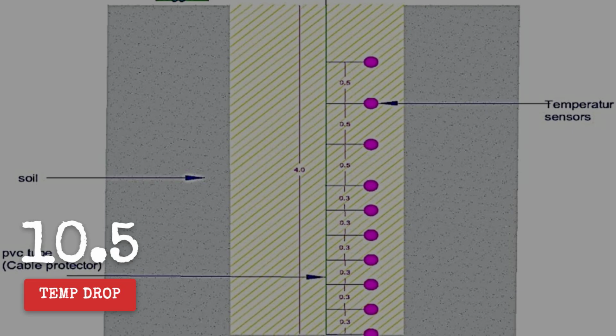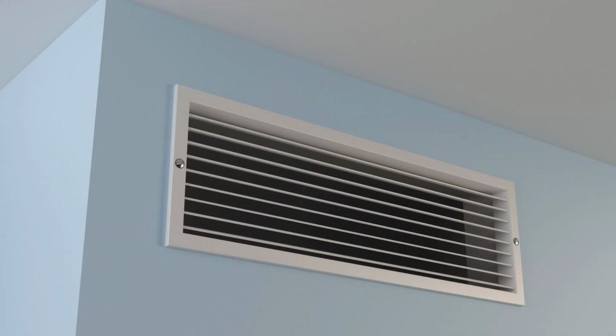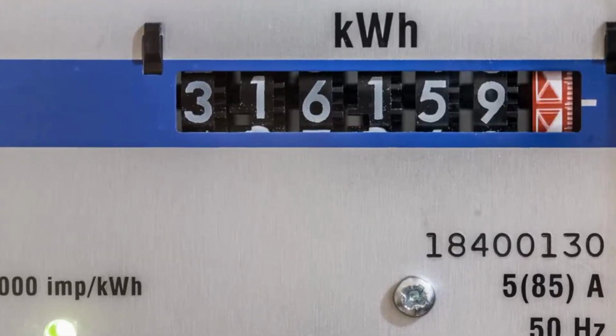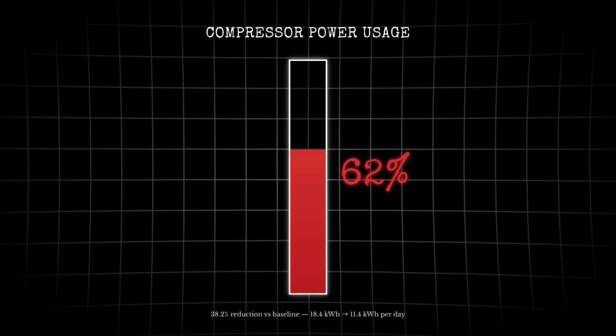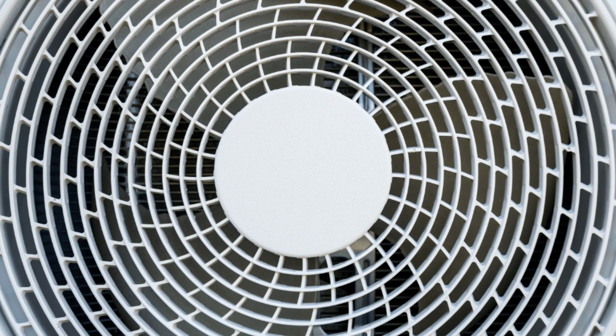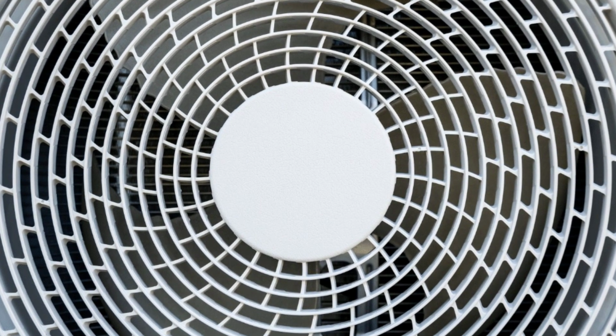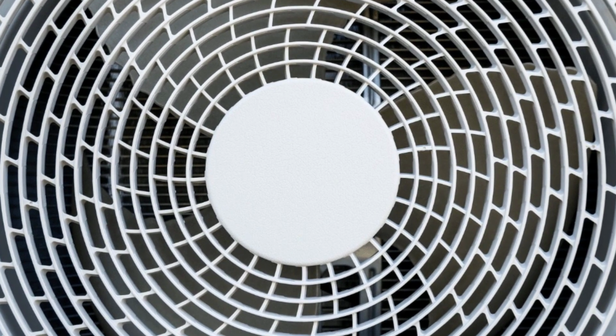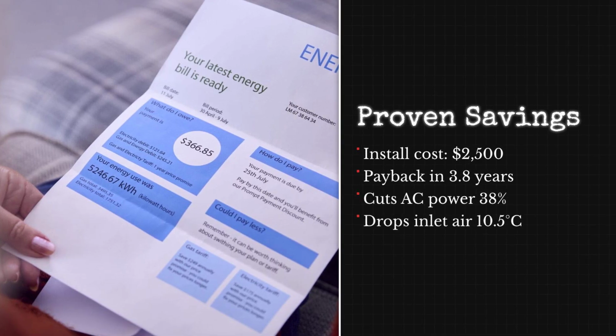Sensors at the inlet and outlet showed a temperature drop of 10.5 degrees Celsius, and air entered the home noticeably cooler than the ambient environment. The impact on energy use was just as clear. Electrical monitoring revealed a 38.2% reduction in compressor power for the home's standard HVAC unit. With a capital cost of $2,500 and a measured payback period of 3.8 years, the numbers speak for themselves.